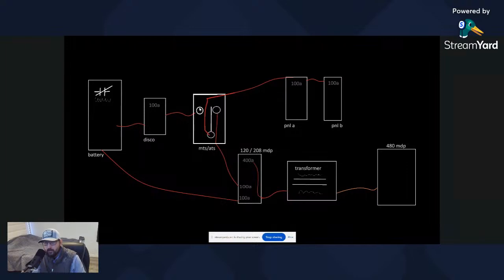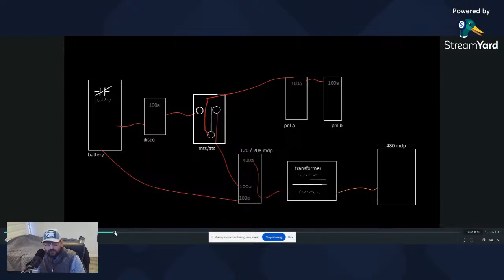And then this would determine on what status we are. So in the event that we lose power, if we lose power here, if the building goes down, we're going to no longer get power here. So this will be off. This, however, will turn on because it's going to sense the loss of power. You see these contacts here? You got normally closed, normally open. So this is usually closed, which allows current to flow to this disconnect, which allows the power to be sitting here. When this opens, it senses that it lost power. That's the low voltage opening. And now the battery is going to supply power.